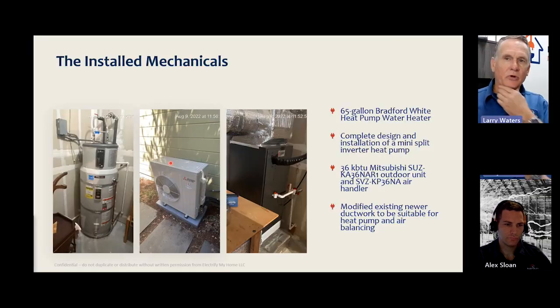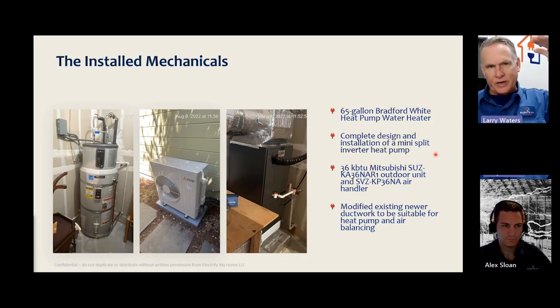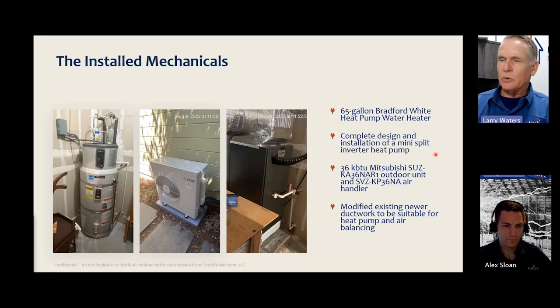The installed mechanicals were a Bradford White 80-gallon or 65-gallon heat pump water heater, and a completely designed installation of a mini split inverter heat pump. I originally gave them the option to put a system in the attic and another one downstairs so they could split it all off, but they decided to reuse the existing ductwork because it was on a system from '98, and the ductwork had been replaced during a previous remodel, so we went with that.